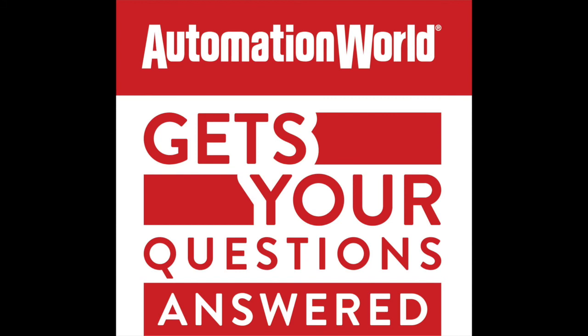Now, you've mentioned numerous benefits of IO-Link in our discussion here today, but for those who are interested in the technology, are there any potential downsides or caveats that they should be aware of? That is a really good question, David. And while IO-Link adds a lot of these benefits, you've got to understand that IO-Link is a point-to-point communication and it is not a network. So it is completely transparent from the control level network.